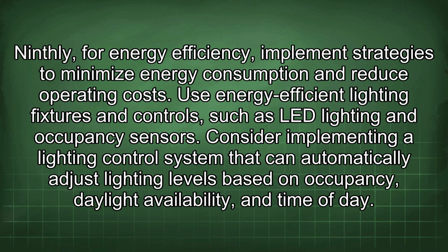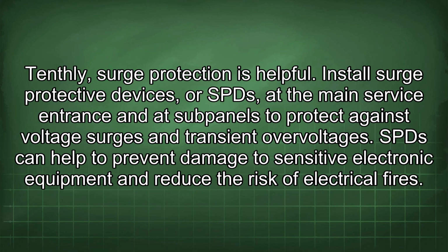Ninthly, for energy efficiency, implement strategies to minimize energy consumption and reduce operating costs. Use energy-efficient lighting fixtures and controls, such as LED lighting and occupancy sensors. Consider implementing a lighting control system that can automatically adjust lighting levels based on occupancy, daylight availability, and time of day. Tenthly, surge protection is helpful. Install surge protective devices, or SPDs, at the main service entrance and at subpanels to protect against voltage surges and transient overvoltages. SPDs can help to prevent damage to sensitive electronic equipment and reduce the risk of electrical fires.